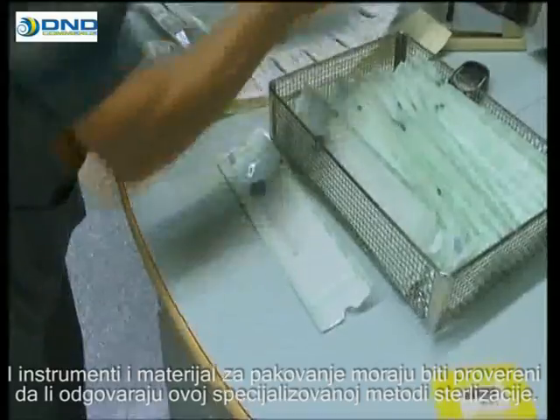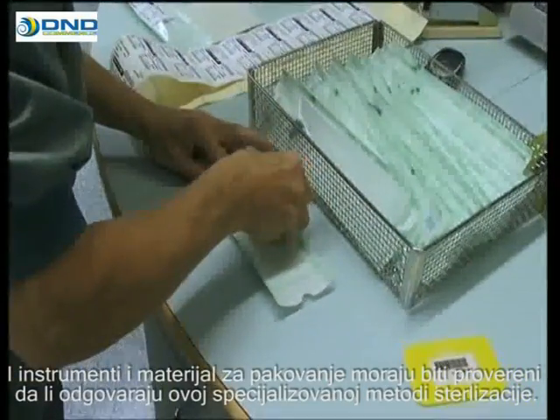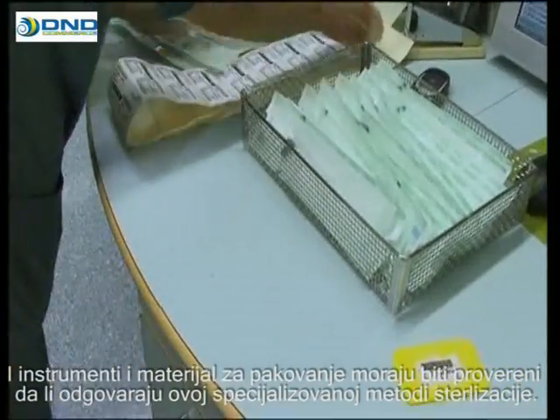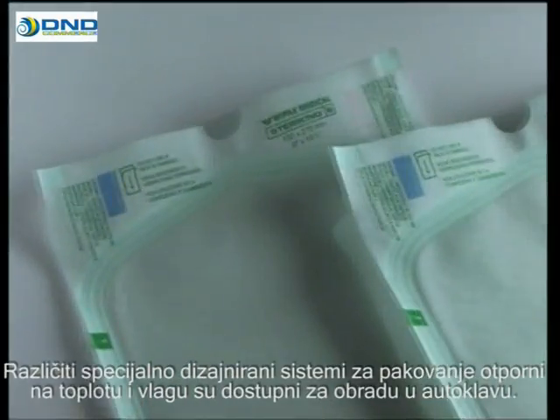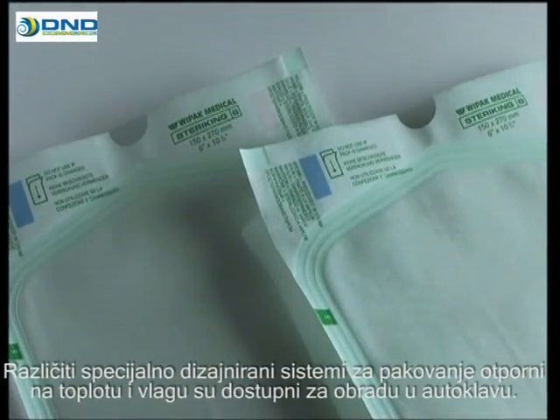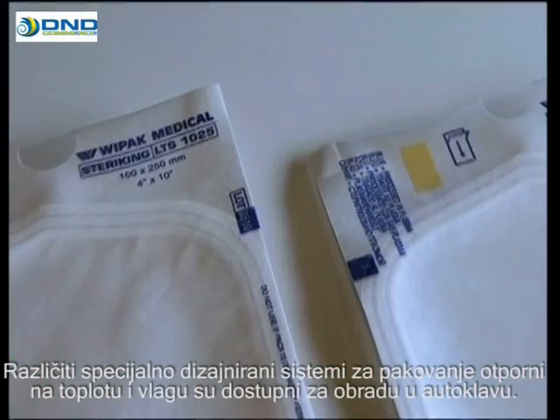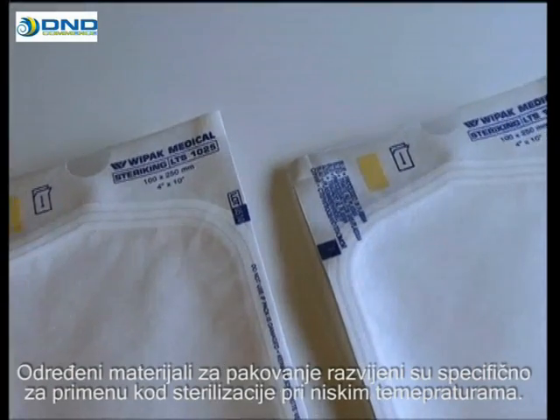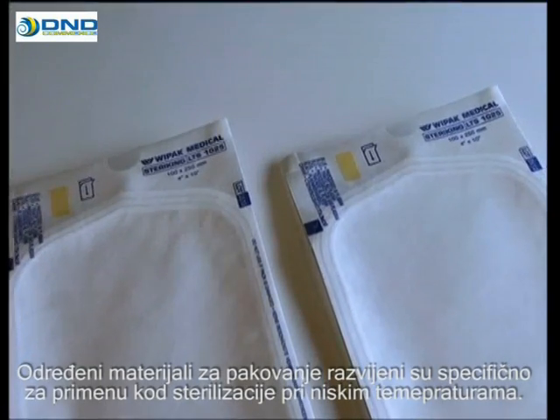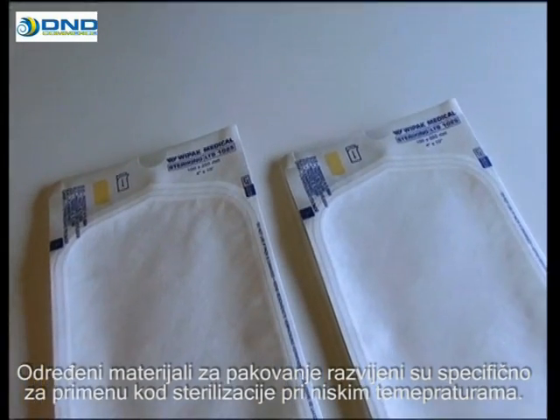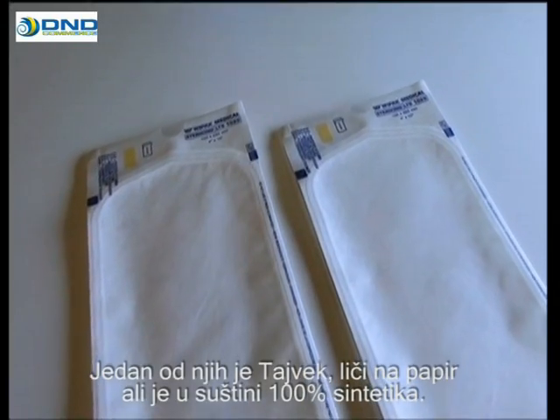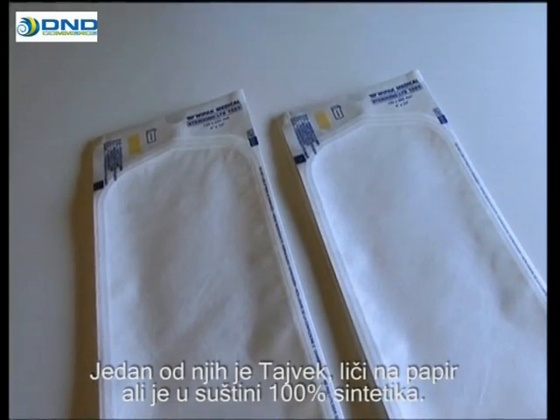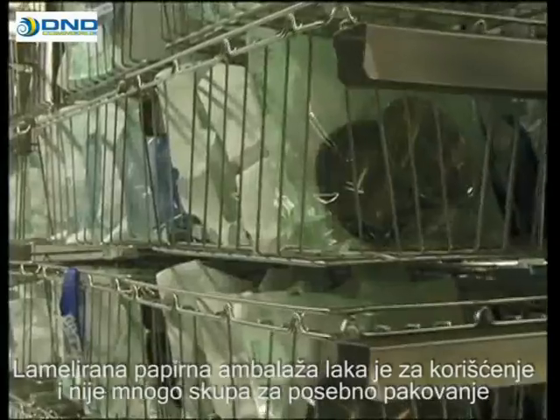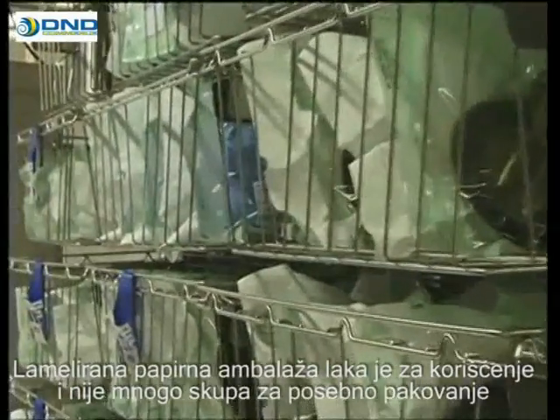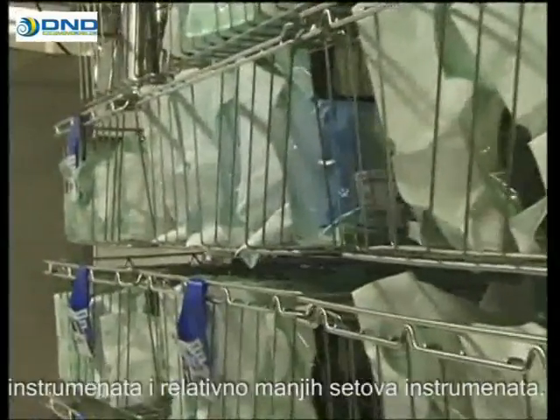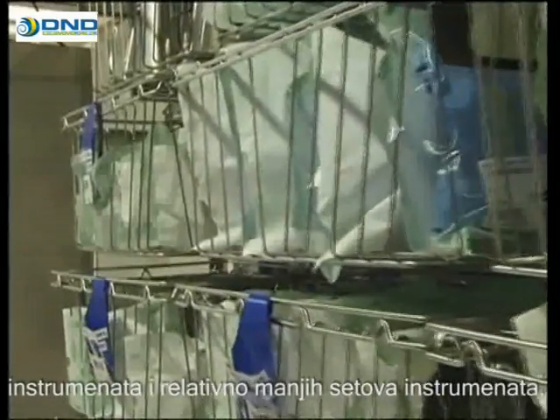Both the instruments to be packed and the packaging materials have to be checked as to their suitability for the specific sterilization method involved. Various specially designed heat and moisture-resistant packaging systems are available for autoclaving. Certain packaging materials have been developed specifically for low-heat sterilization. One of them, Tyvek, resembles paper but is in fact 100% synthetic. Paper laminate packaging is an easy-to-use and cost-efficient solution for packaging individual instruments and relatively small instrument sets.